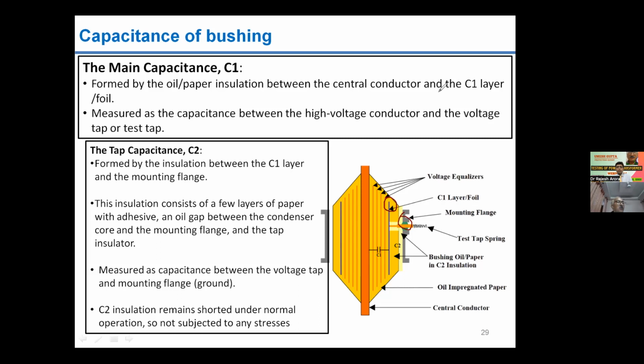Because if you don't earth the outside layer of the foil, the grading of the entire insulation will not be even. So the outer foil is grounded, connected to the earth, and accordingly we measure C1 and C2. In the field, many times we ignore C2 because it is just an indication of the health of the connection between the outer layer of the foil and the connection which comes out of the foil to ground it, just to assess its health. So many times we do not refer to it, but it is important. Okay, next.